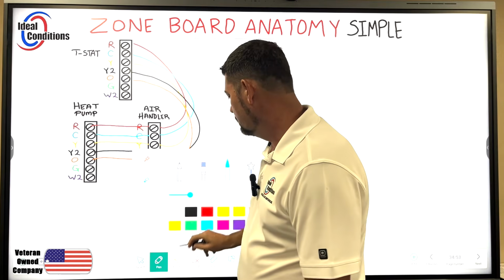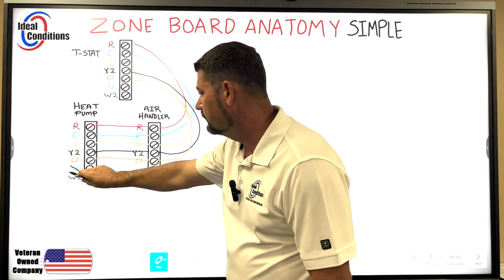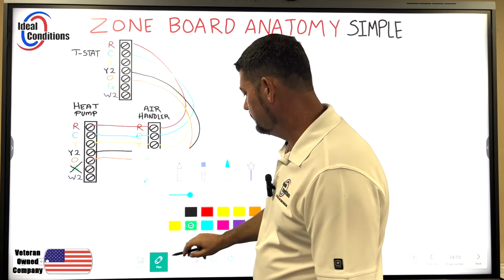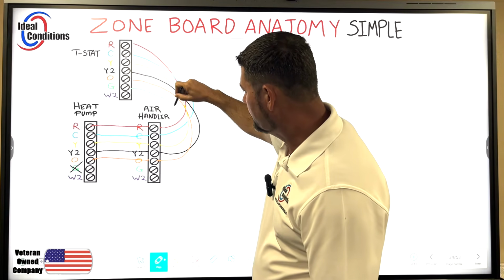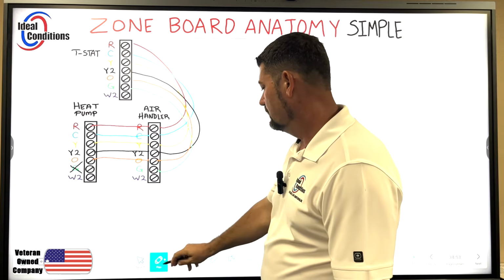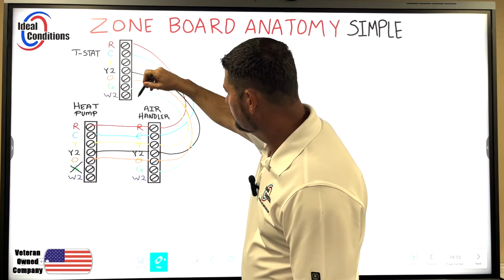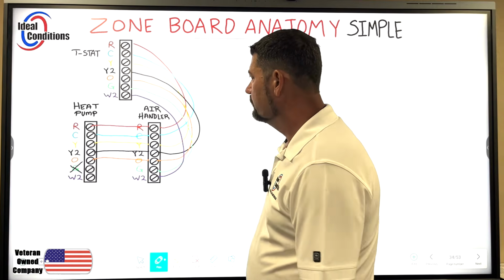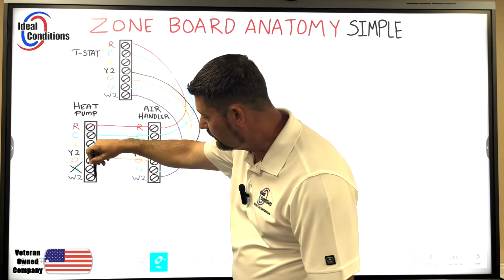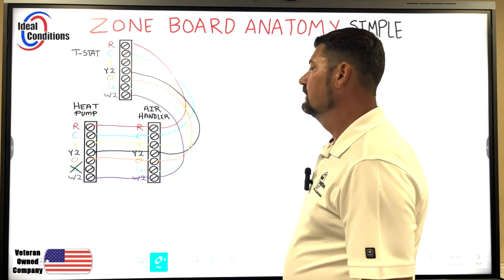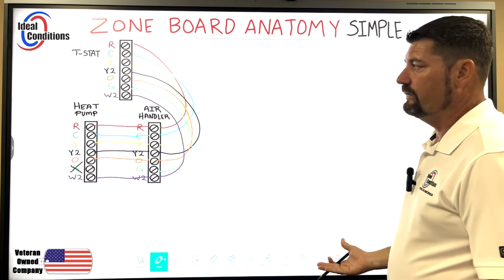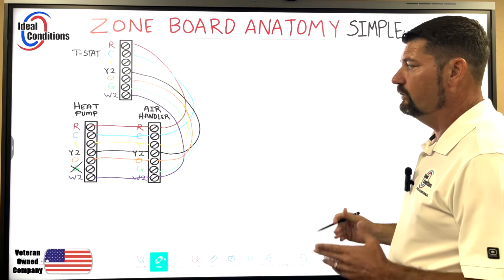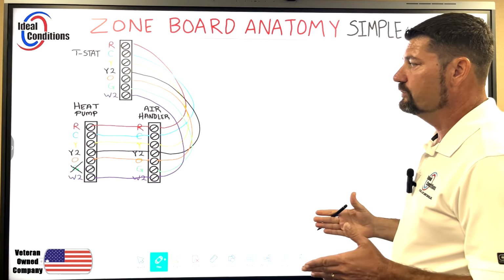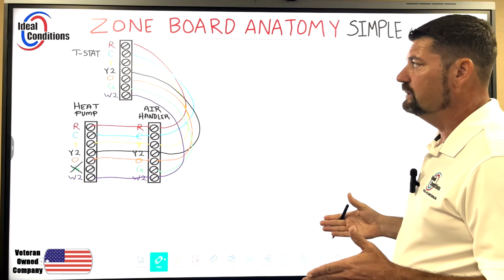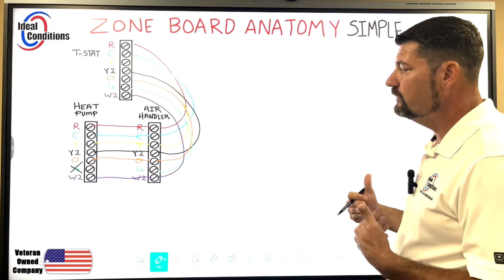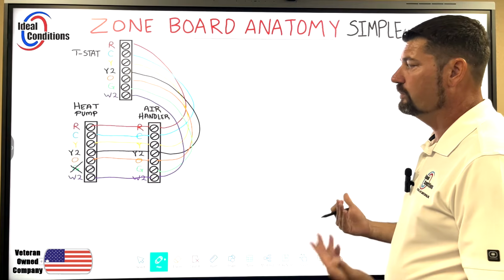Now I did put a G over here, so I'm going to go ahead and just say there is no G. So we're just going to put an X on that. So let's go ahead and go to G now. Coming out of the thermostat, we're going to go right into the air handler, and that's it. Same way, W2, out of the thermostat over to the air handler, and then out of the heat pump, coming back this way. And that's it. So there's nothing difficult about that at all. And so there's no zone equipment here, there's no dampers, that's just an air handler, your heat pump condenser unit, and one thermostat. The moment you start integrating more thermostats, we're going to cover that.